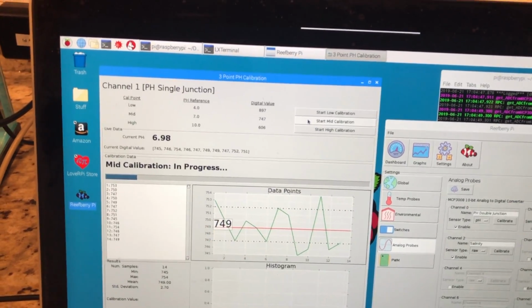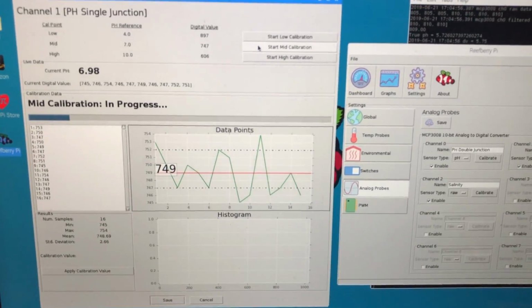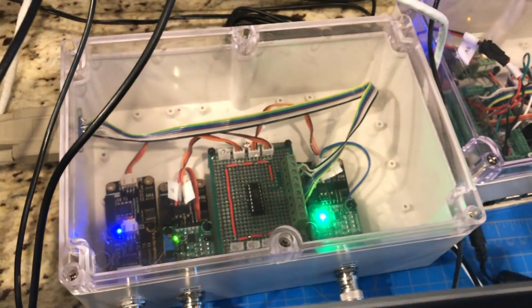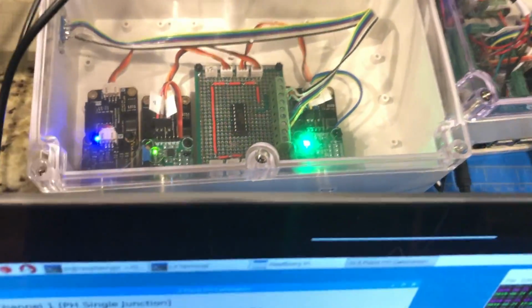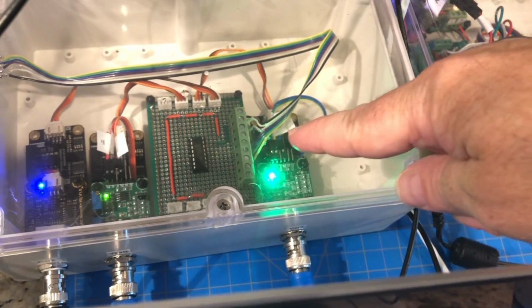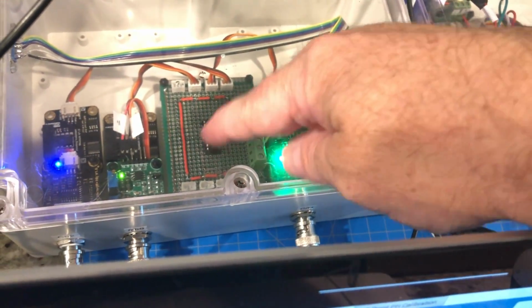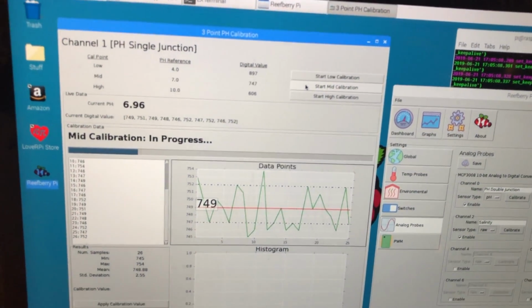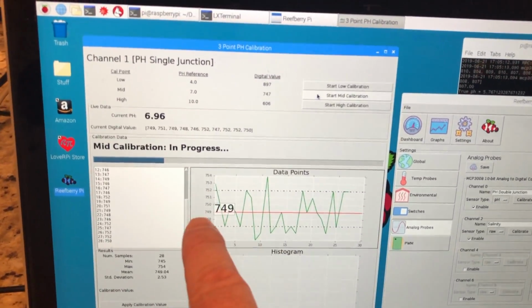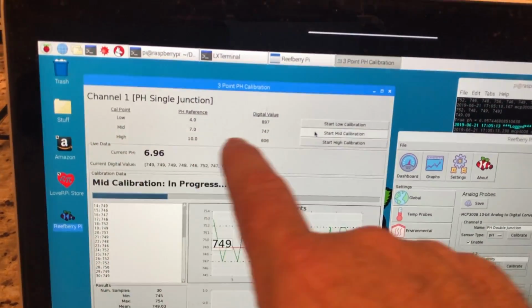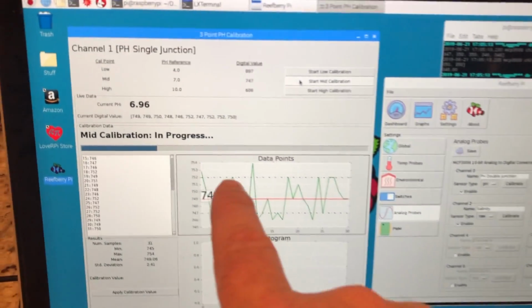And this number represents the A to D counts that are being read, because those probes are sending out an analog voltage. The Raspberry Pi will not read that, so they send the data in here, and this converts it to a number, which is being read right here. So basically that number 749 equates to 7.0, or whatever this number happens to be at the end.